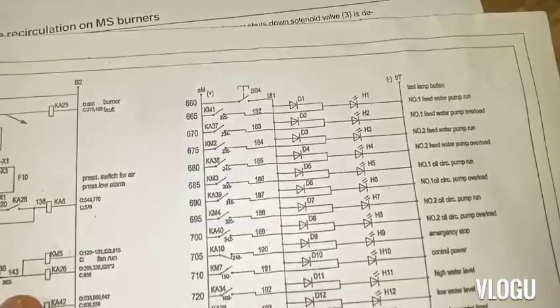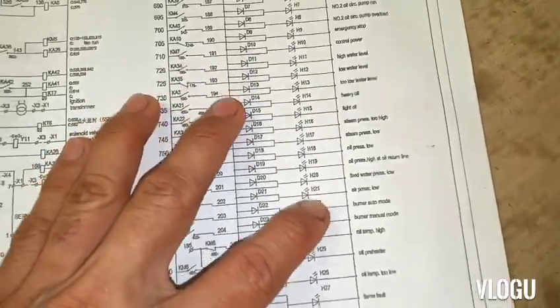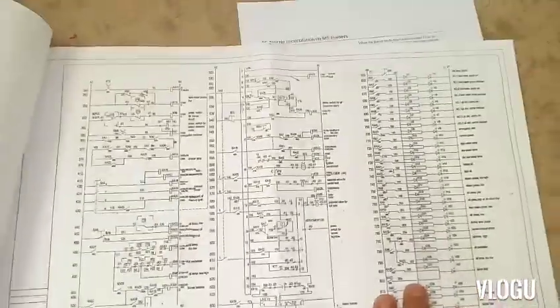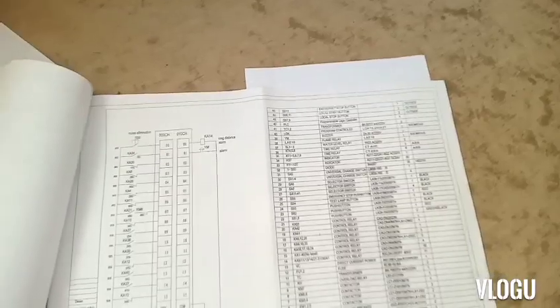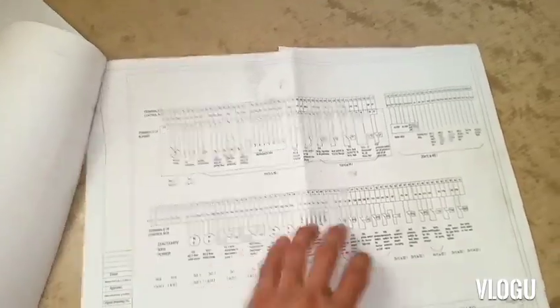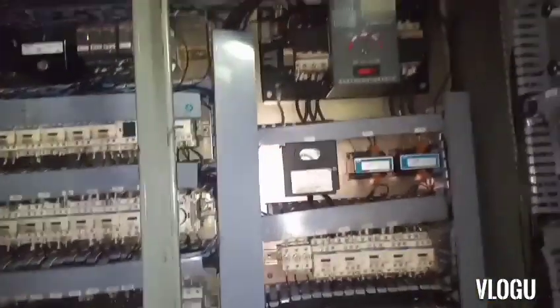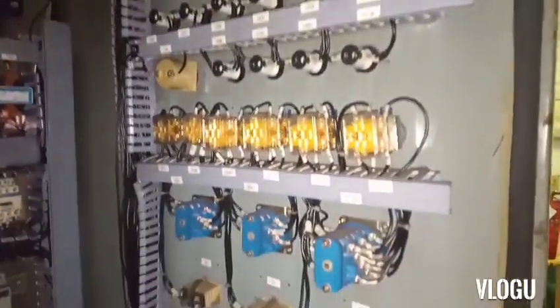The problem is we cannot run in auto and we cannot run in manual mode, and there's no alarm showing. After reading and downloading the manual for this burner controller, all you need to do is push the glass to reset the burner controller, and after that you can run the boiler automatically.